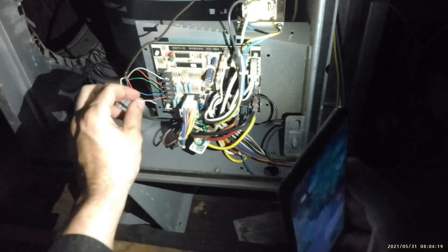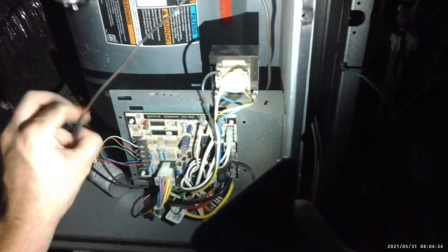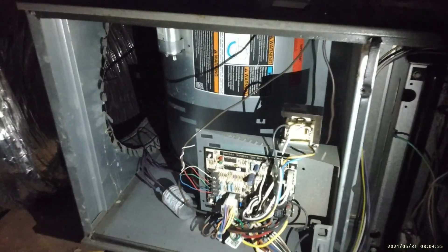There's a way you can actually use this same wire without replacing it. What you're going to do is use your red wire, and then cancel out the common wire. You're only using one wire to crank up your unit. And if you notice — the unit's going to come on — it came on now, you can actually hear the gurgling. So it did come on. I'm going to show you outside what you have to do to make this work.